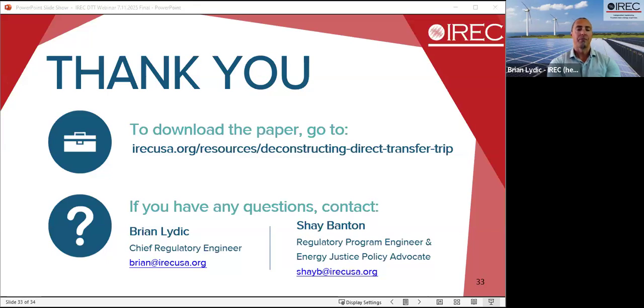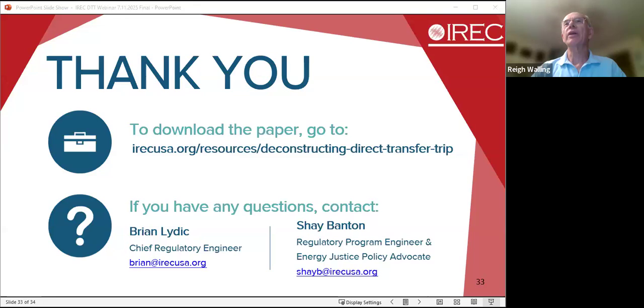Right. And the other might be a circuit that you frequently drop as a matter of practice. I think that's pretty rare, but you might have a circuit that you move between sources, and the sources have a big phase difference, so you have to do a cold transition or an open transition, moving the circuit from one source to another. I think utilities avoid this because it blinks out customers. But if you did have a circuit that you're doing that frequently, obviously we'd want to take a closer look. But I think in general, it's sort of fruitless because, what will it really tell you?